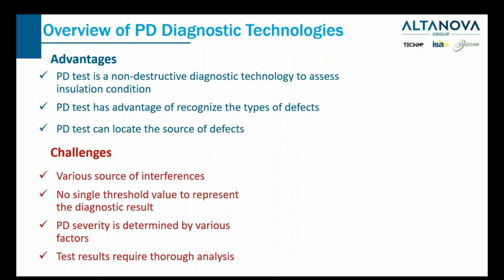If we're comparing the corona discharge, which is external to the equipment under test, to the internal cavity discharge within the insulation system: if the corona discharge is huge, like thousands of picocoulombs, it does not do much damage to the insulation system. So it's probably very safe to operate under thousands of picocoulombs of corona discharge.